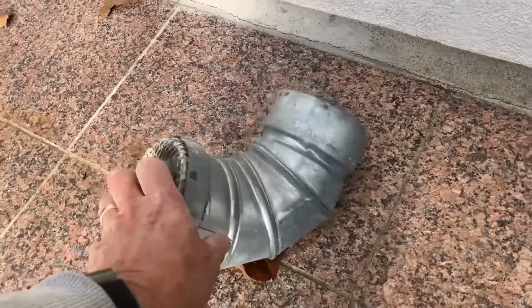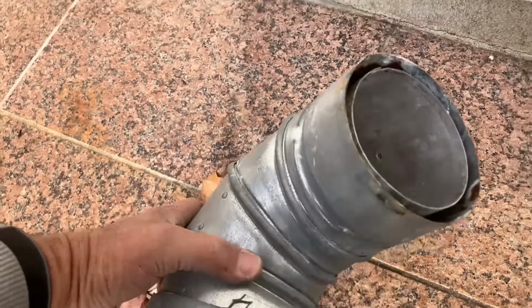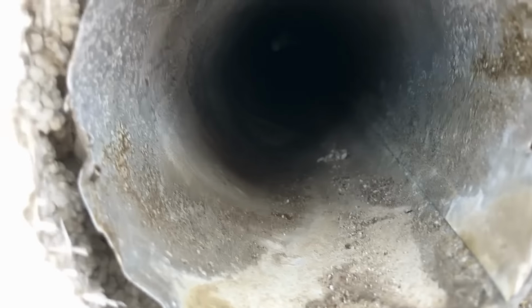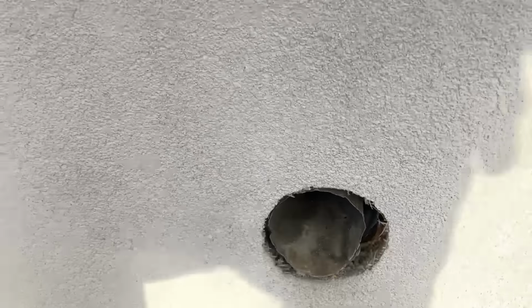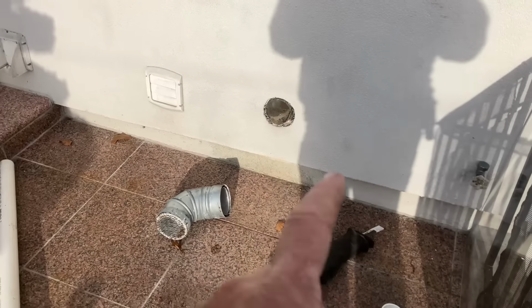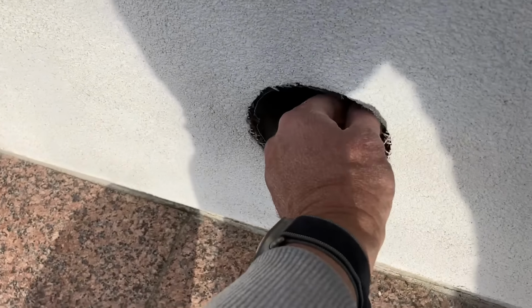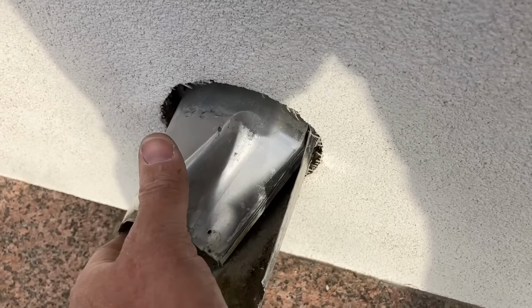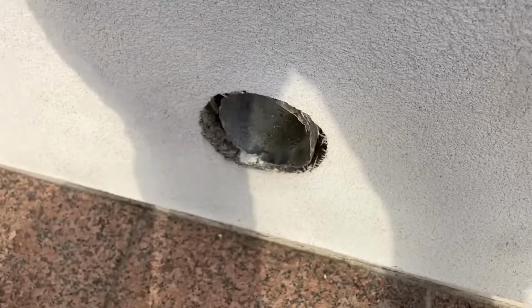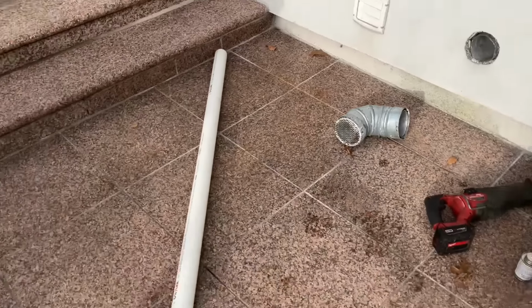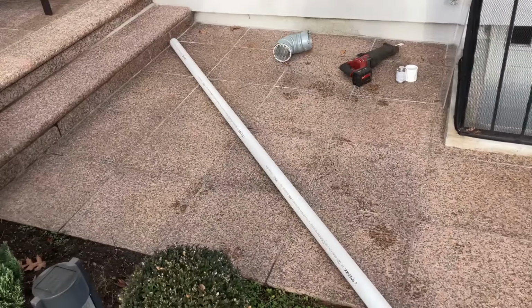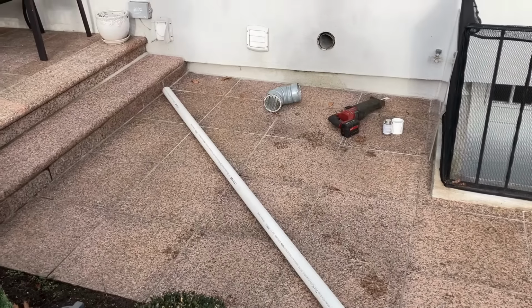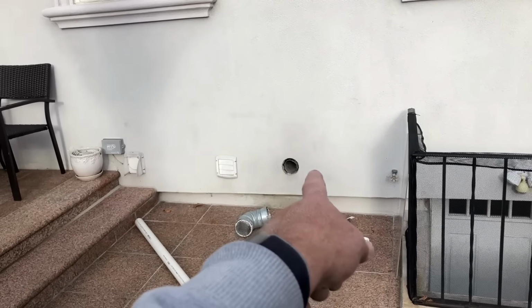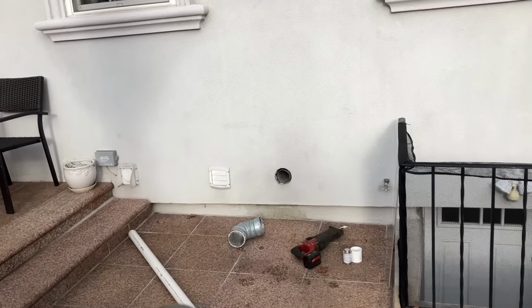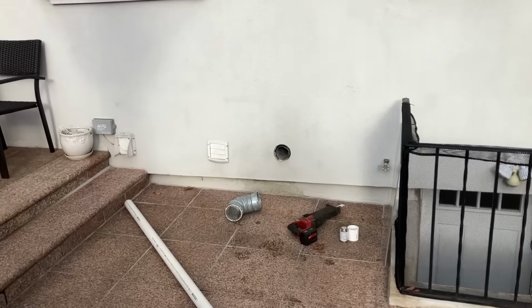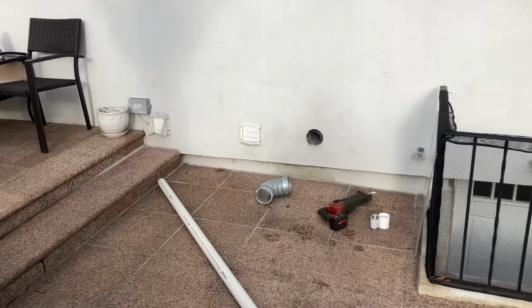So here's that piece of fake B vent. Well, it's a real B vent 90. Going to this dryer vent. So I'm going to use that 4-inch dryer, and it is dryer vent because look how thin walled it is. See? It's dryer vent. So I'm going to use that as a chase for a length of 2-inch PVC for my fresh air. We'll pull fresh air from where the exhaust was, and the exhaust is going to be on the other side. They also have another chase that's being used for a condensate.